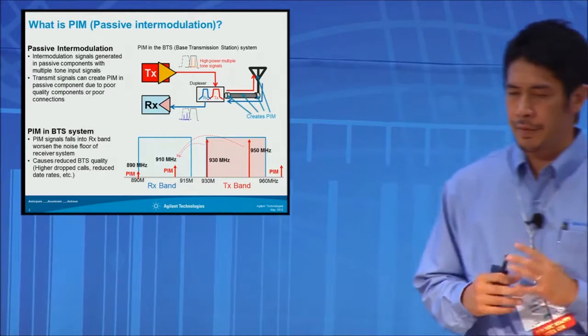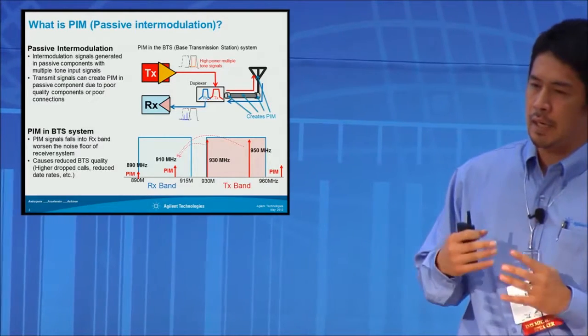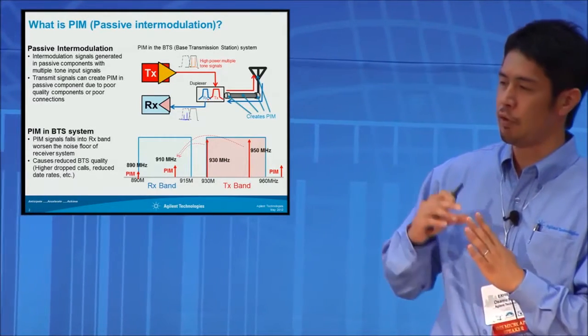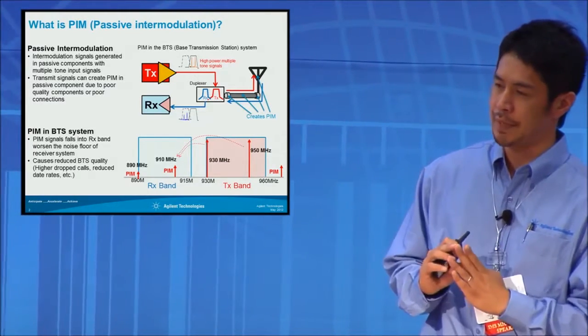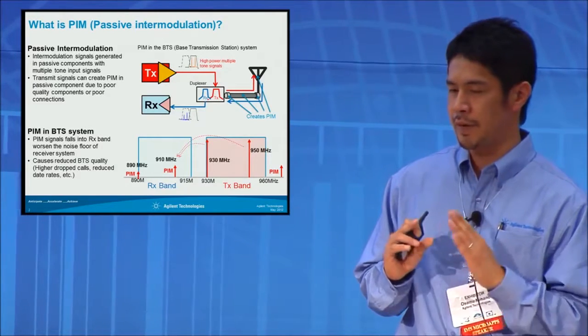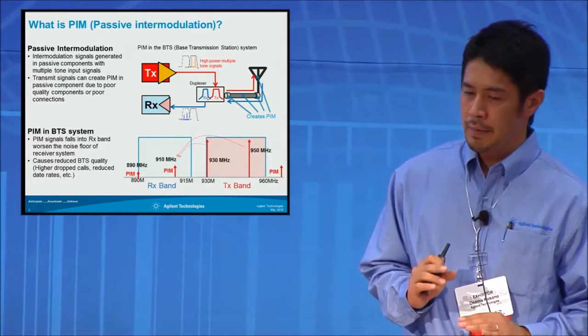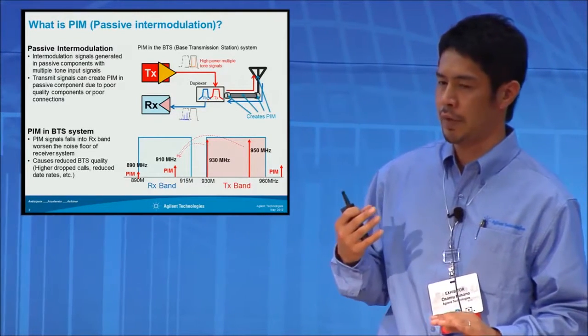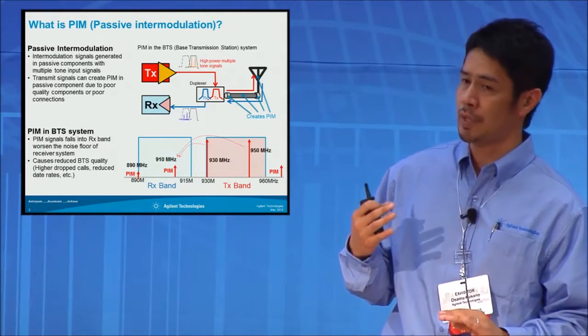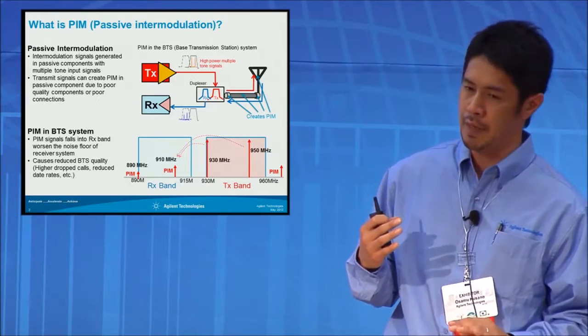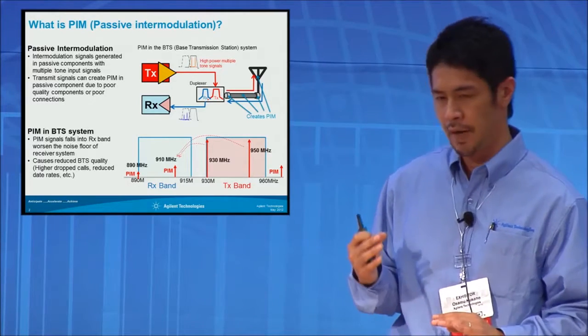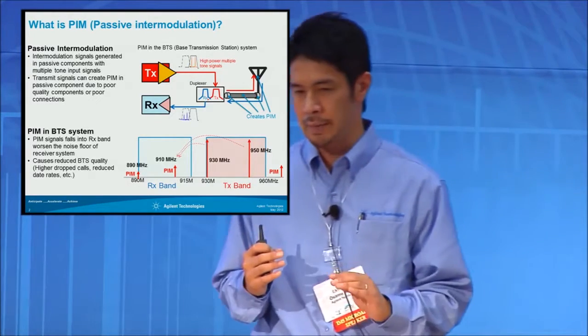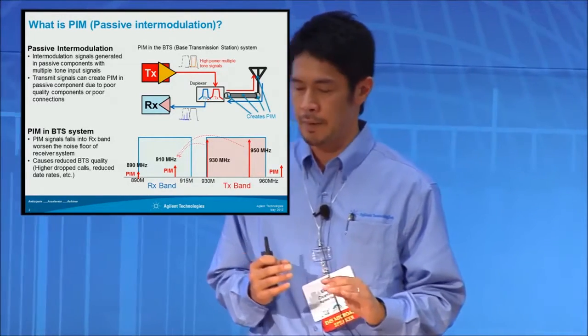It is difficult to measure passive intermodulation in a normal case because passive intermodulation is very small. But if you put high power — like 20 watts or 43 dBm — to the passive device, you can actually measure PIM, and it is a problem.